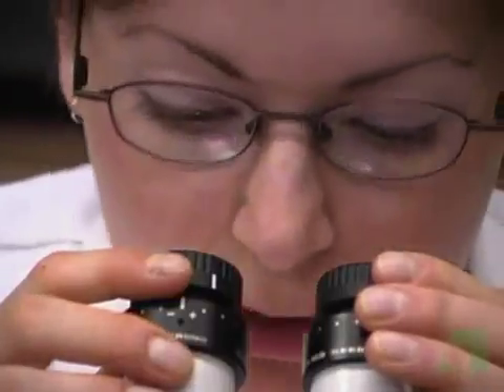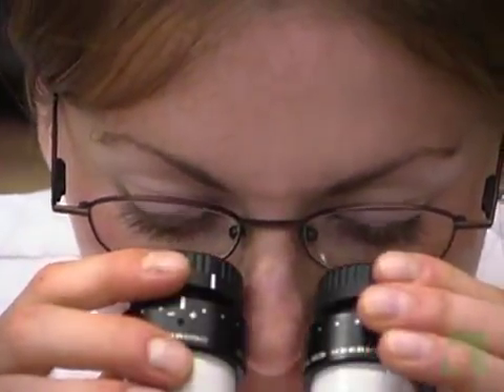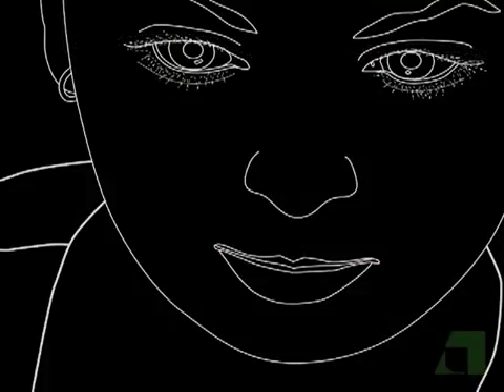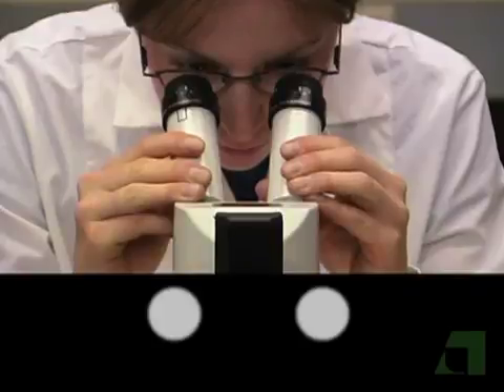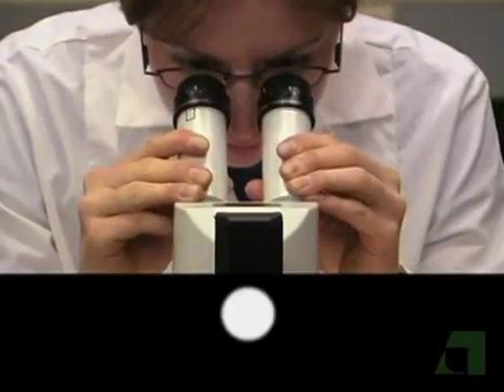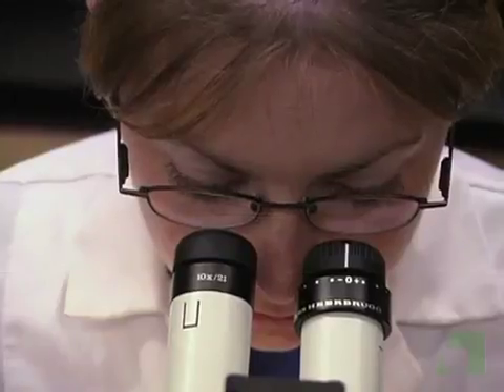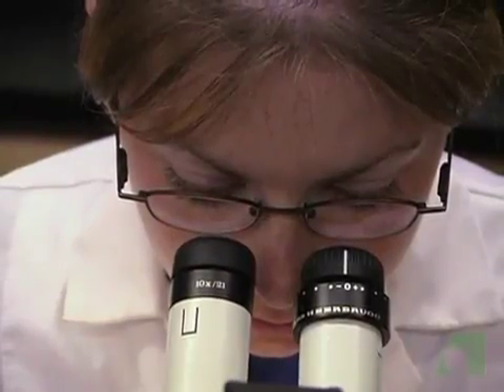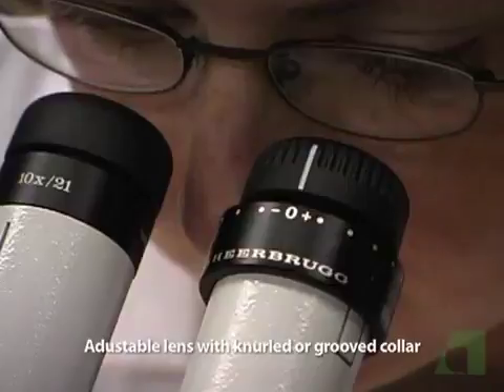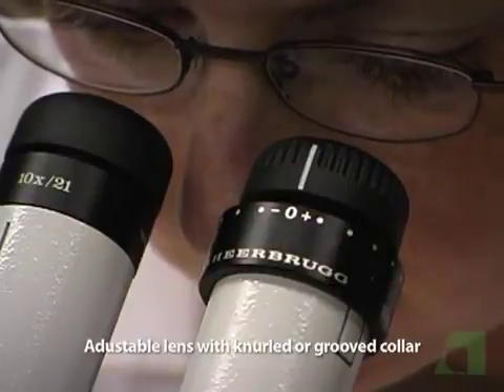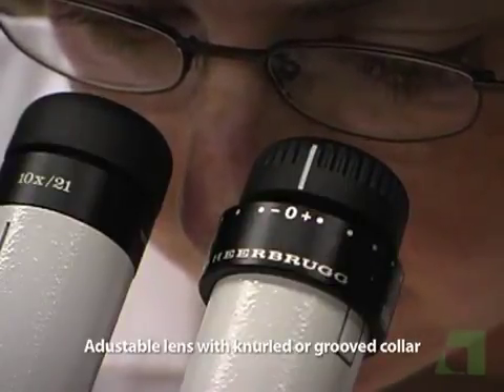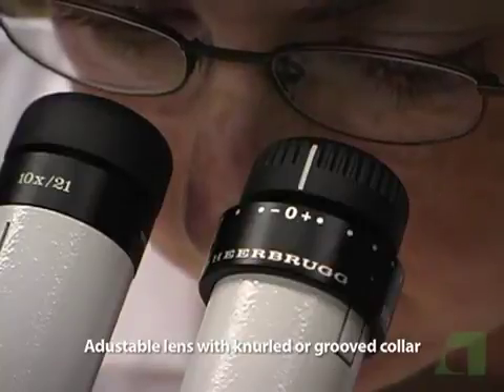Look into the ocular lenses and move your head up and down until you see the largest image. If you use eyeglasses, you may choose to wear them or remove them. To make the interpupillary adjustment, move the ocular tubes together or apart so that you can see only one circle of light, not two circles. To make the diopter adjustment, first determine which one of the two ocular lenses is adjustable. Usually, this is easily detected by the presence of a grooved or knurled collar.